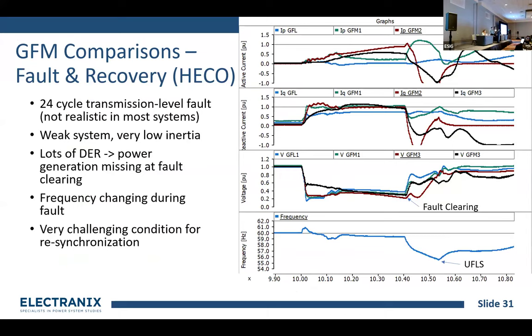Another example focusing on a different part of the response: the event we're looking at is a prolonged fault — almost half a second, a delayed clearing fault. The system is very weak and very low inertia, and at fault clearing around 10.4 seconds, the load in the system picks up again but our DER has a slower recovery timeframe, so there's a lot of energy missing on the system briefly — a power mismatch in the system that somebody has to pick up. This is a very challenging condition for grid forming inverters. This is probably the kind of test that's going to break grid forming controls, because we have a long period of time where the inverters have to limit their fault current, and they may have to freeze some states and then also deal with the frequency dropping by half a hertz during that time and then pick up a bunch of megawatt and megavar load coming out of the fault. The system does eventually get saved by UFLS.